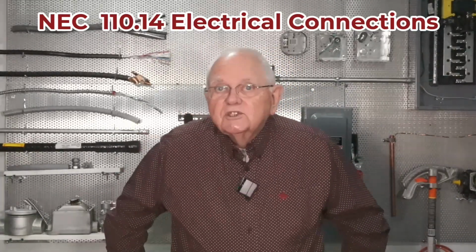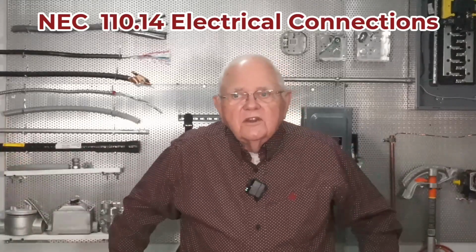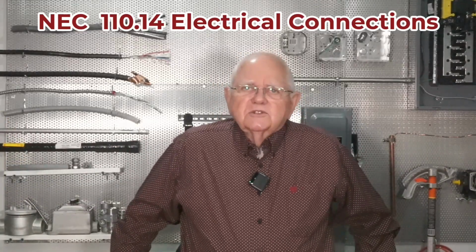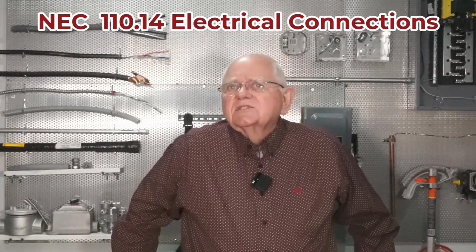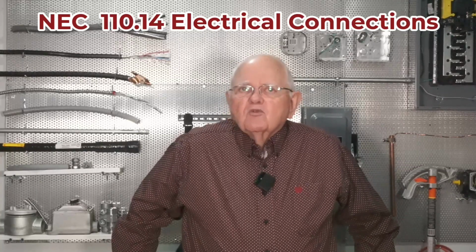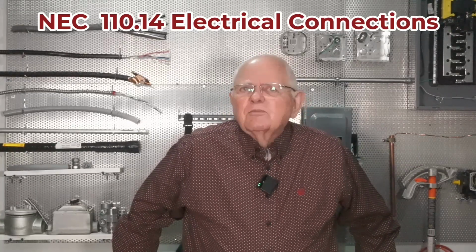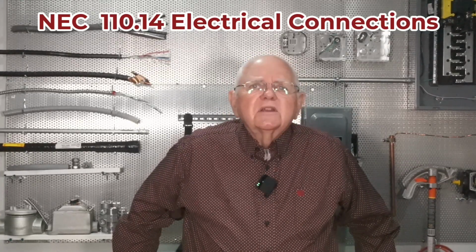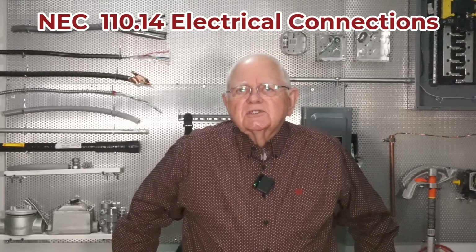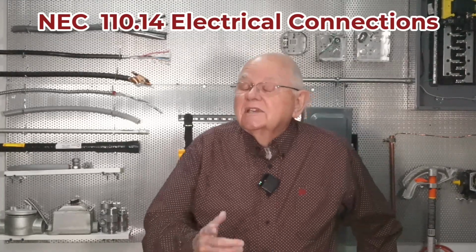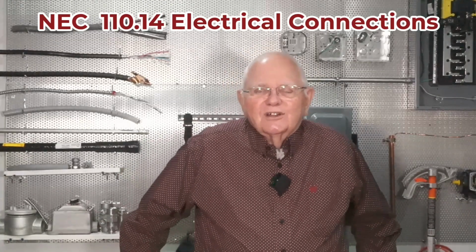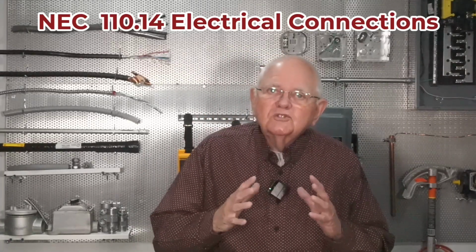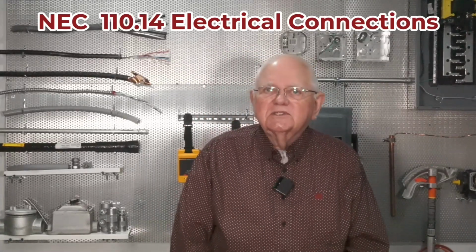Well, it's steel, should be 0, right? Yeah, if I could go from end to end on that rebar, it's going to be 0 ohms of resistance. I bet not if it's got rust on it. Rust is a real good insulator, and you'll probably get open circuit, OL, on your meter when you try to read resistance across that rebar. I think we did that in one of the earlier tech talks a long time ago. If you scrape some of that rust off, you would get pretty close to 0 ohms on your multimeter. So corrosion is a big issue for us between dissimilar metals.